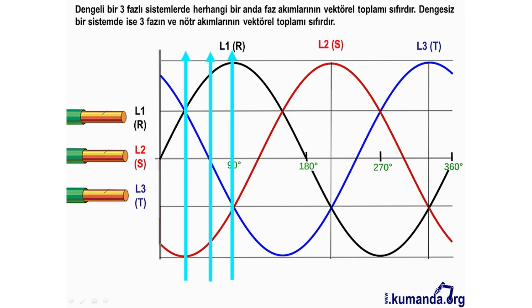3 fazlı sistemlerde: dengeli 3 fazlı sistemlerde herhangi bir anda faz akımlarının vektörel toplamı sıfırdır. Dengesiz sistemde ise 3 faz ve nötr akımlarının vektörel toplamı sıfırdır. Eğer bir toprak kaçağı oluşursa bu denge bozulur, fark akımı oluşur ve bu fark akımı da toroid nüvesi üzerinde manyetik alan oluşturur. Oluşan hata akımlarında RCD açma yaparak koruma sağlar.